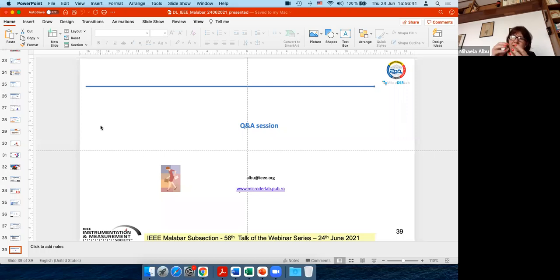Unfortunately, the measurement uncertainty is inflating — by any calculation, it's larger — and this has to be taken into account. So yes, we need artificial intelligence algorithms for processing the information carried by the measurements. But I'm afraid that before reporting, we already pollute the information, we already lose some of it. We just have to tell the user: you will take the 230.2 volt measurement, but the associated uncertainty is 20%, not 1%. We have to announce this somehow. This was my intention.